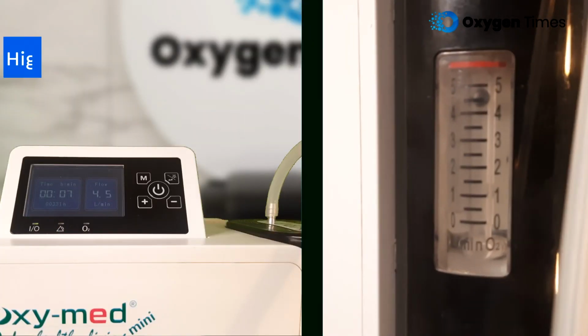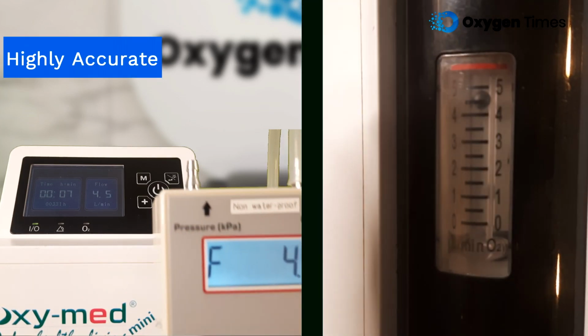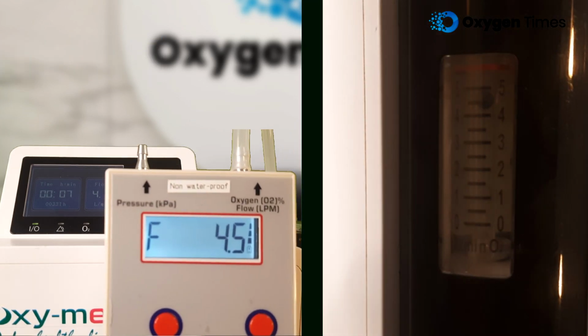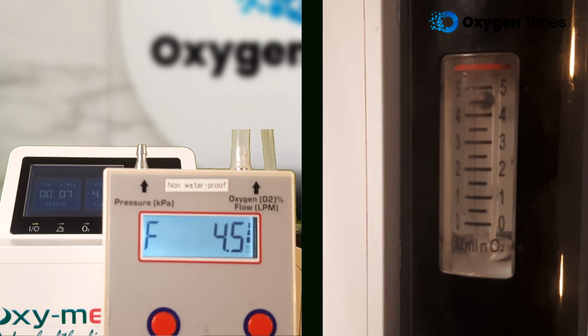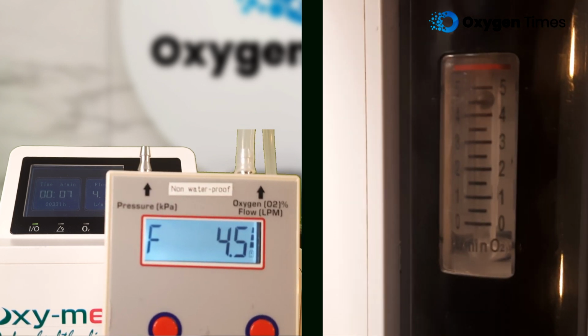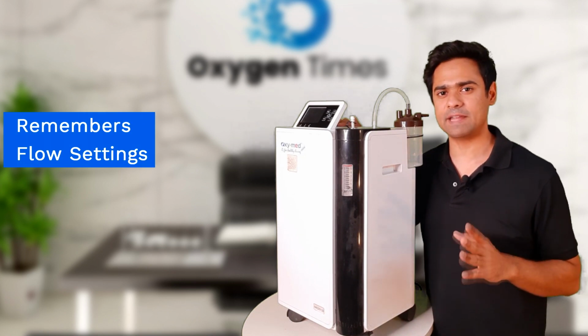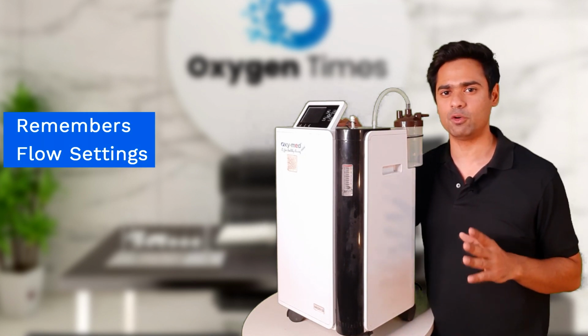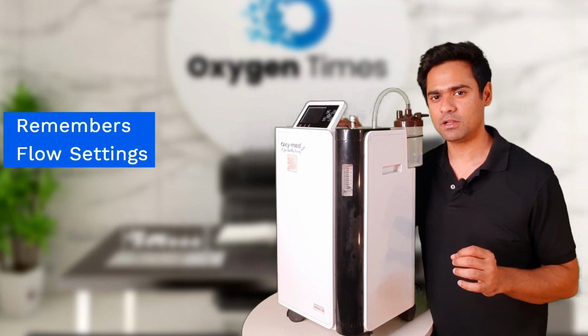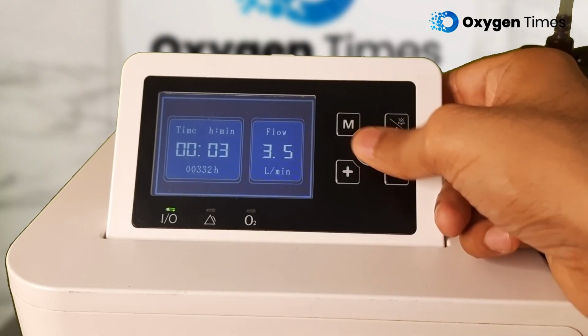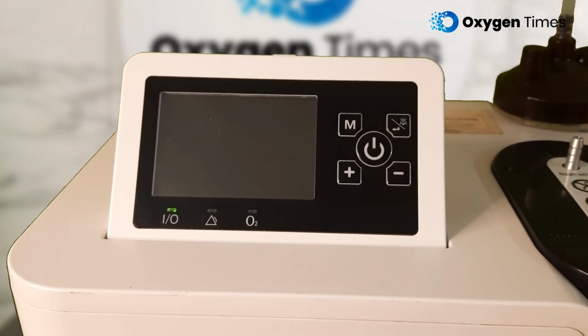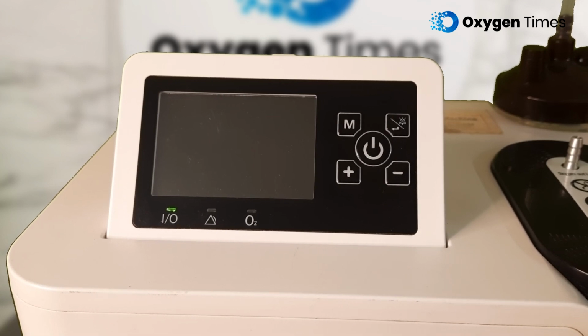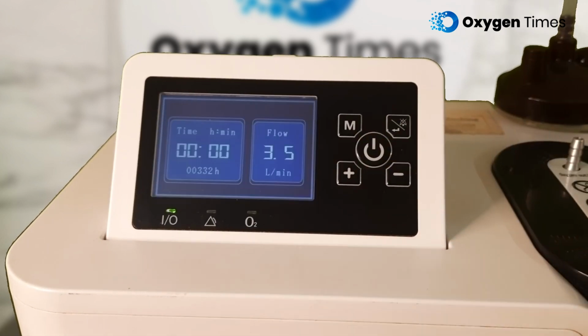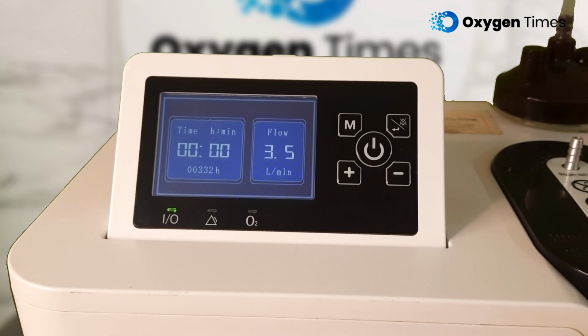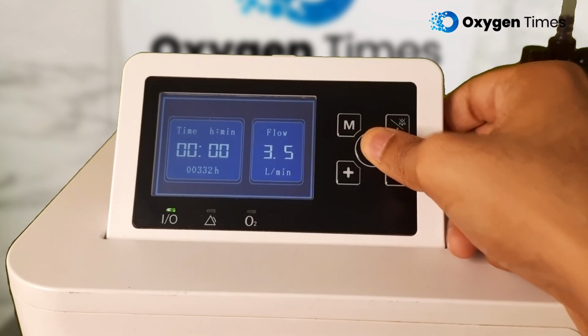Moreover, both the flow meters are highly accurate, as confirmed by our external testing equipment, showing exactly 4.5 with the same setting. The concentrator also remembers the flow setting so that you do not have to set the flow rate each time you switch it on. For example, as you can see, we have set the flow rate at 3.5 liters per minute. When we switch on the machine again, it remembers it well. Oxymed has left even the most renowned oxygen concentrators in the dust with their amazing flowmeter.